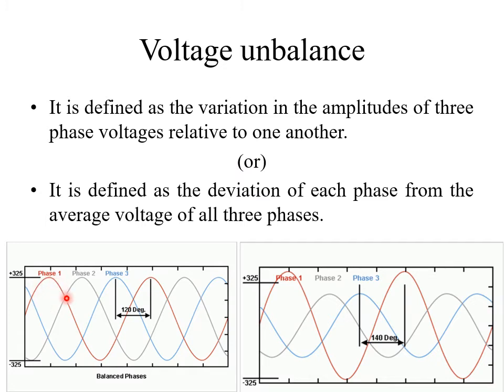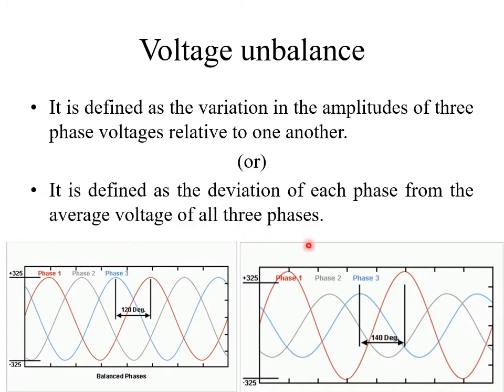In this picture, there are three phases — phase 1, phase 2, and phase 3. The magnitude of all phases is the same, and the phase difference is also the same at 120 degrees. Therefore, this is called a balanced system. In the second picture, the amplitude of phase 1 is different from phase 2 and phase 3, and the angle is 140 degrees, so this is an unbalanced system. Voltage unbalance can also be defined as the deviation of each phase from the average voltage of all three phases.